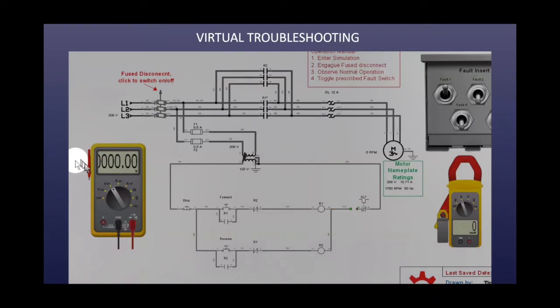The 5 different bugs are typical ones. Trying to do a broken wire, trying to do a high resistive wire, a burnt out transformer where maybe the secondary's been blowing the fuse or it's shorted to the core. Those are hard to put in a lab and swap out a good transformer and a bad transformer in between students. On this one, we can do it.